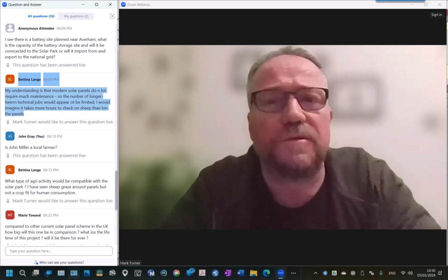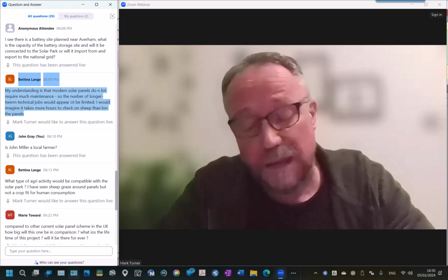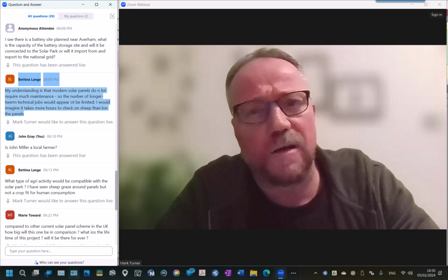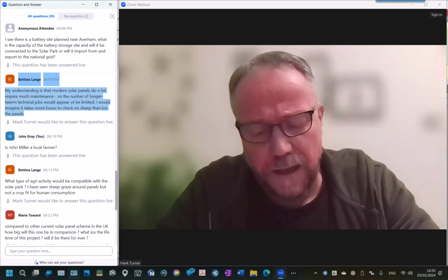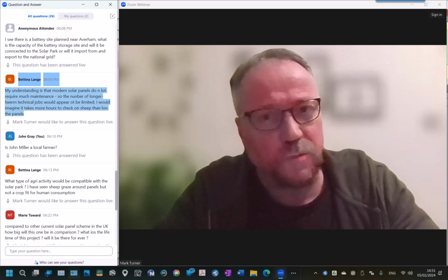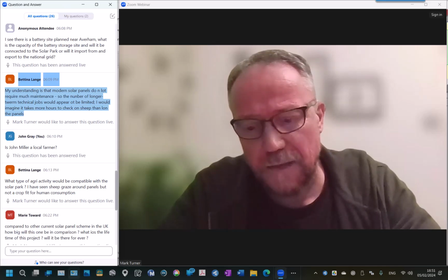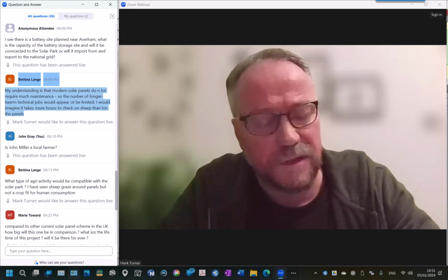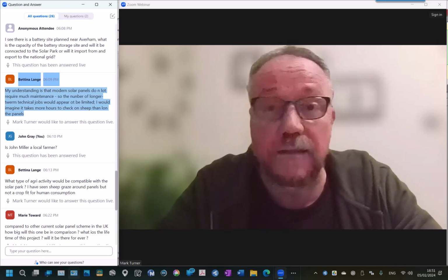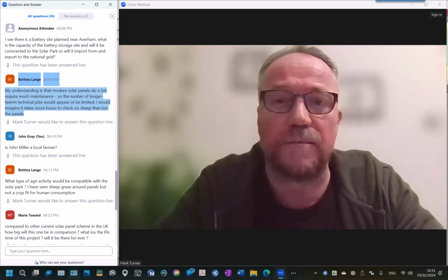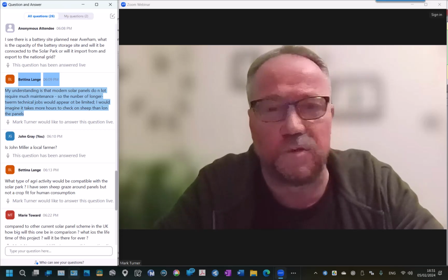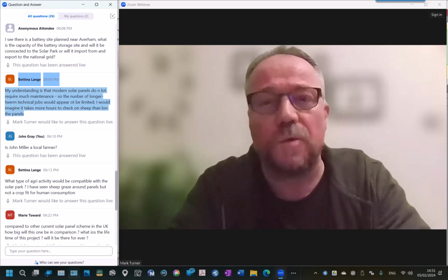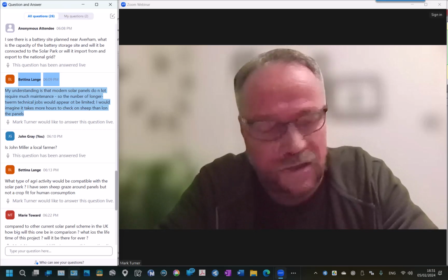Certainly. In terms of maintaining the solar panels, the panels and the associated equipment don't require much maintenance. They do require quite a lot of inspection, separate from actual work, but checking on them. And that's done in a number of different ways. We use drones with thermal cameras once a year to inspect the panels. We inspect the connections with thermal cameras to make sure that the connections are good and we're not losing any energy through resistance.